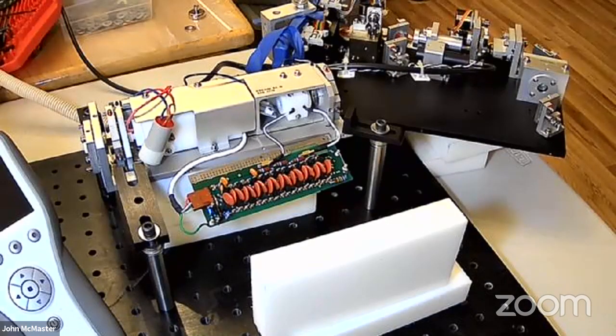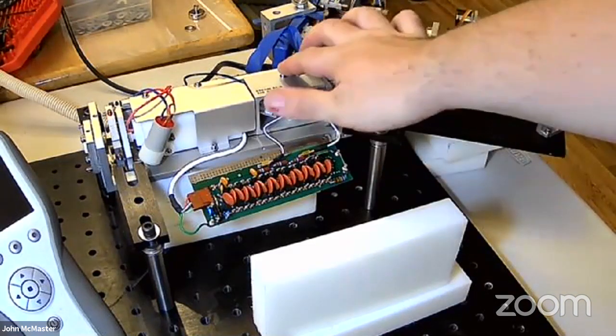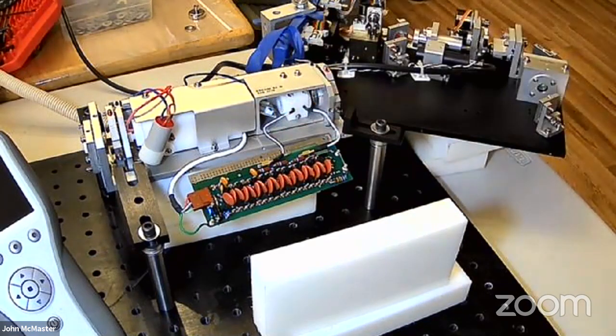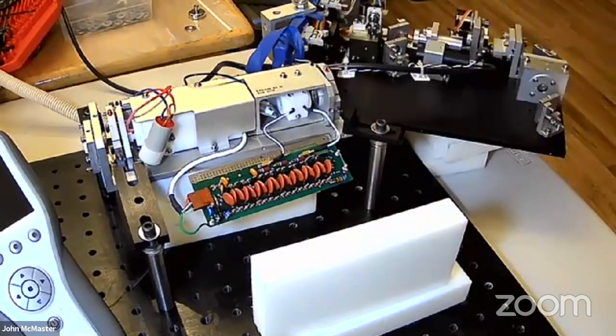Yeah. Well, we're almost done in any case. There's one or two steps left, basically. So now we insert this optical cell back in here. I think if you just insert it with the polarization like we have it, the laser will actually fire, because when this thing is off, it doesn't do anything. So we'll insert this optical switch back in, and we'll realign this XY, just like we did before. We may also do an iterative process where we adjust this position slightly and then have to realign, just iteratively jiggling the optics until the power is good. And then we're almost done, because at this point we have the optical switch installed, but it's idle.